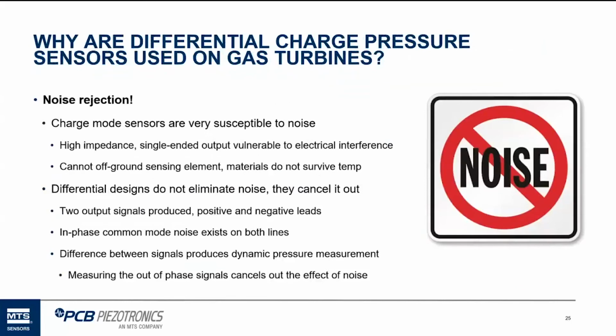So why are differential charge pressure sensors used? Again, we use a differential charge amplifier, and the main reason that's used is it provides noise rejection. Charge mode sensors are very, very susceptible to noise, and a differential charge amplifier actually cancels out the noise by design. It takes and switches the positive and negative leads as necessary. It's kind of a technical, complicated type of device, but it's able to cancel out the noise so that you're just getting the actual signal from the sensor, and then it's able to take that signal and provide an output, typically a voltage output.